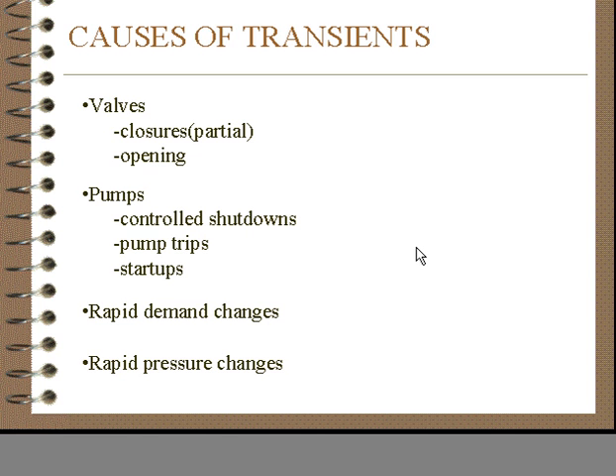This presentation deals with the data required to describe the cause of transients. The causes of transients are valves opening and closing, pumps, controlled shutdowns, startups, or trips where the power fails to the pump and we have an uncontrolled shutdown, rapid demand changes such as a fire hydrant opening and closing, and rapid pressure changes.